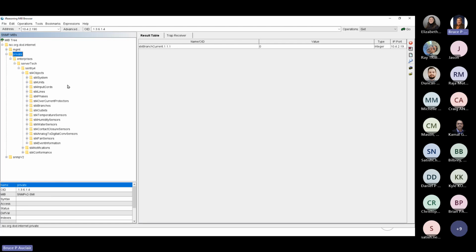Okay, I think maybe our introduction mentioned looking at power, which would be active power or watts. That is something that a lot of people are interested in. Another object could also be energy. Active power, watts, is the dynamic power usage at the moment that you're polling that object. Energy is consumption over time, so kilowatt hours or watt hours, depending upon which level you're looking at.